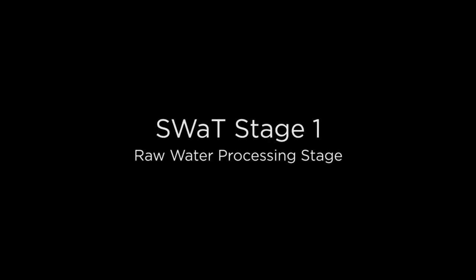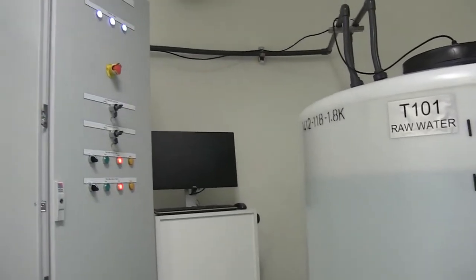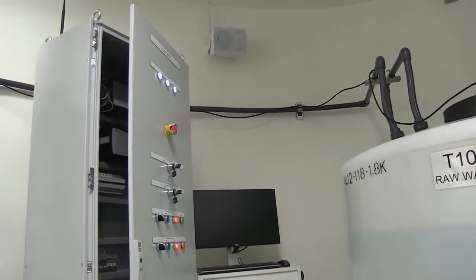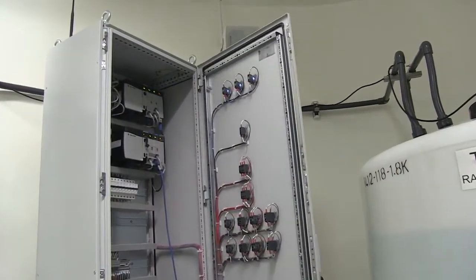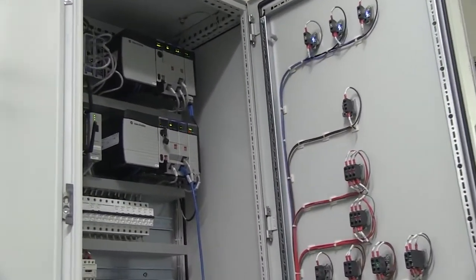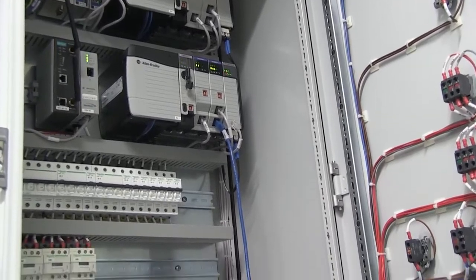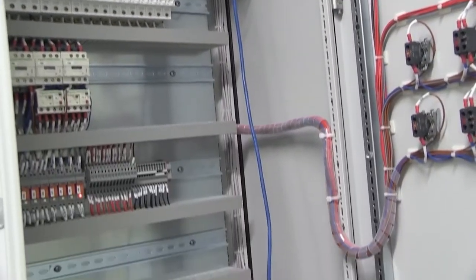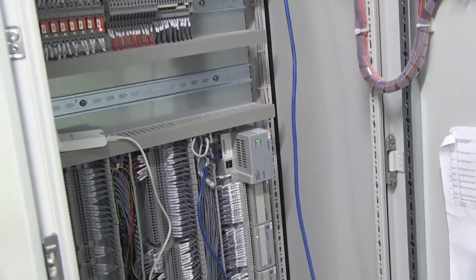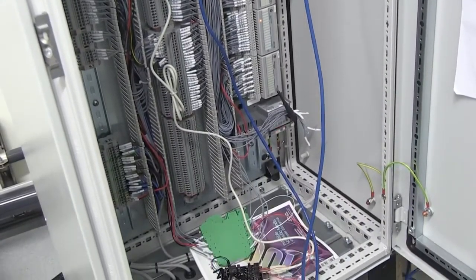We are now at Stage 1 of SWaT, also known as the raw water processing stage. This is the control station for this stage. It contains dual Allen Bradley PLCs. One PLC serves as the primary and the other as backup that immediately takes over when the primary fails. Each of the six control stations in SWaT is configured with a dual PLC configuration. The purpose of the controller at Stage 1 is to manage the flow of raw water from the inlet to Stage 2.